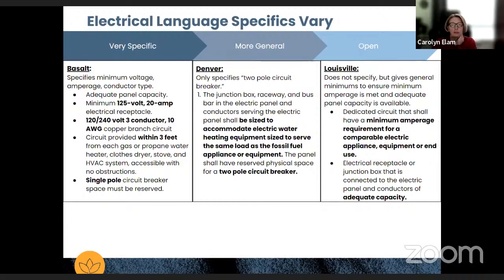Just one thing, the electrical capacity is not there already, just for the outdoor condenser unit. If you go all electric, you still require the capacity for the backup resistance heat. So if you think about the furnace as an indoor location, you may still need that additional service capacity.